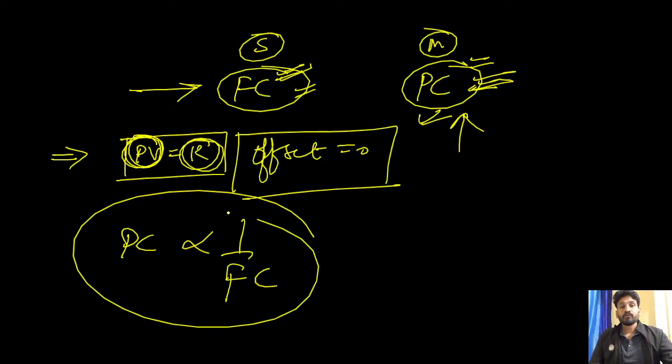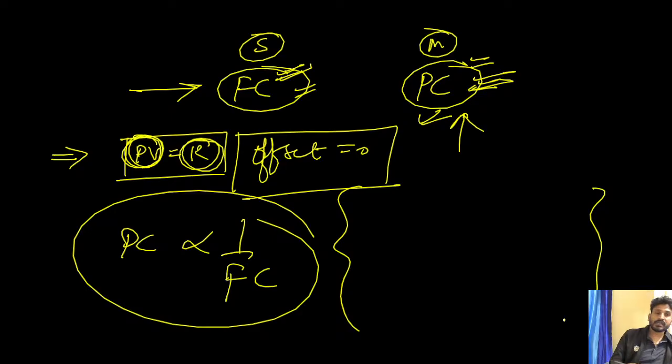ठीक है. So first of all, whatever we have the option, in that option, अगर ये bias value का offset 0 वाला कुछ ऐसा क्वेश्चन आता है, तो ये इंफॉर्मेशन आप ध्यान रखेंगे. That what is the master control, what is the slave control, and at offset 0 we feed some value in the PC and we feed some value in the FC. And the value of PC and the FC are inversely proportional. Means at the lower pressure signal, my flow controller will be high.